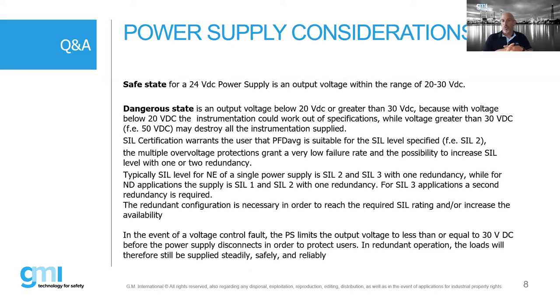So safety power supplies can alert you in case you have lower or higher values of voltage, protecting you by that. So you have an alert on that. The output is protected from 30 volts by the overvoltage protection. So the dangerous state is something that is really avoided by having a safe power supply.